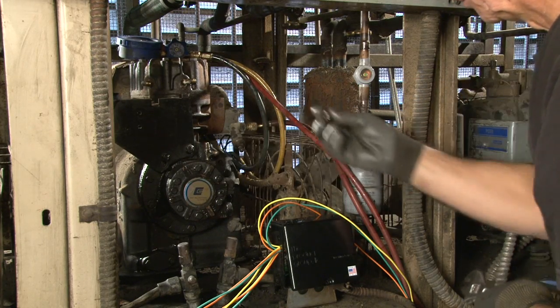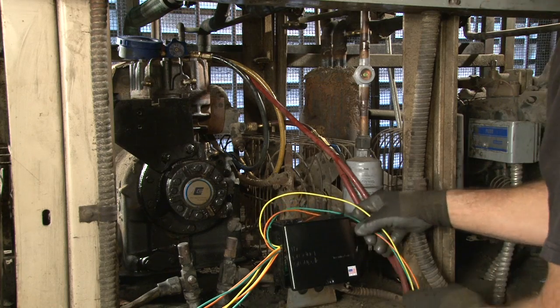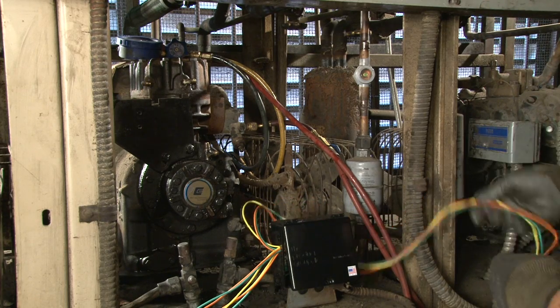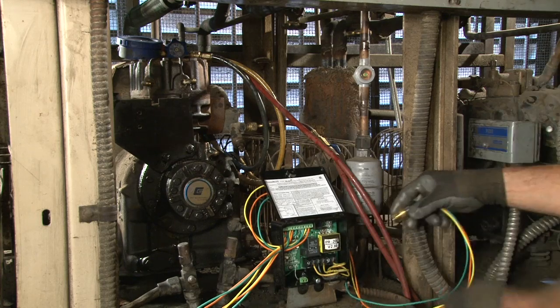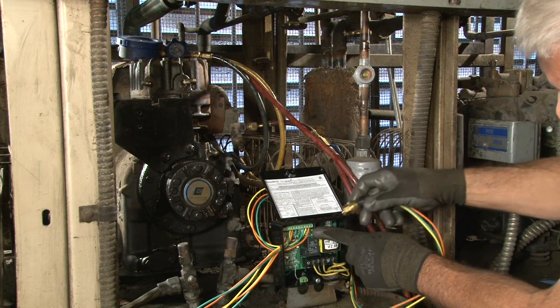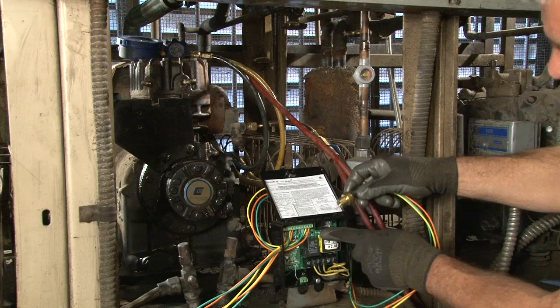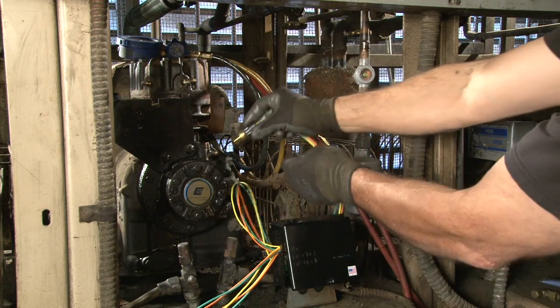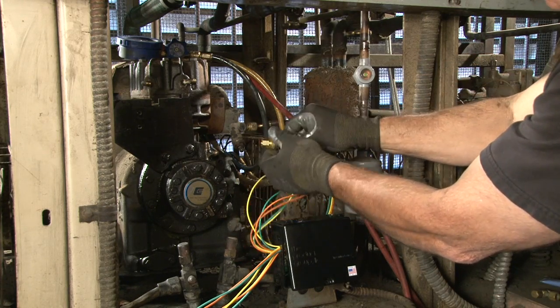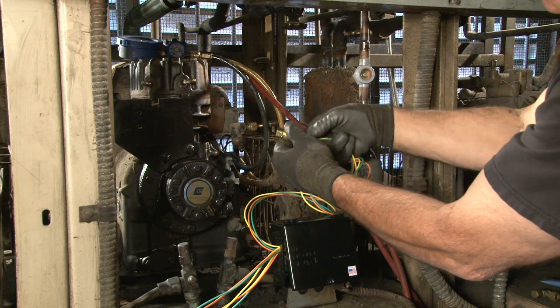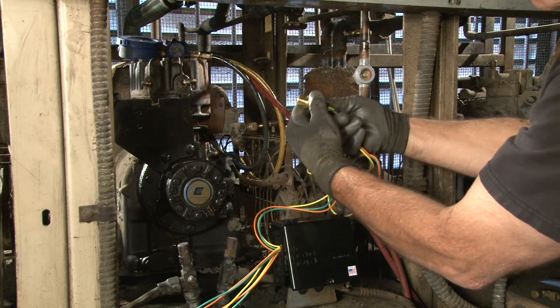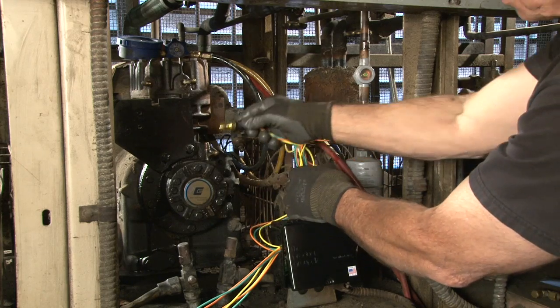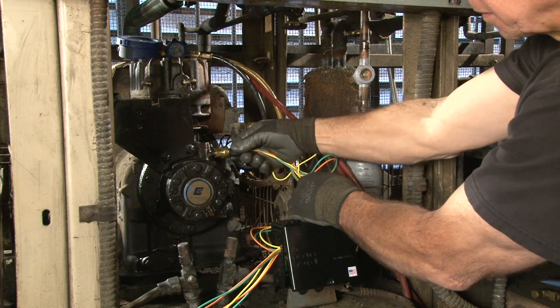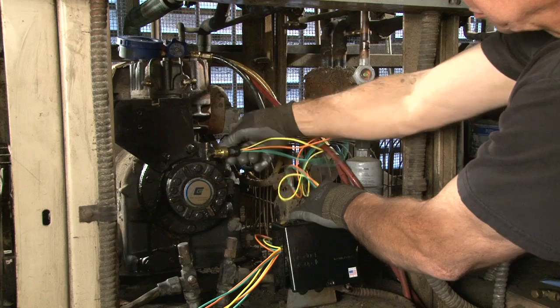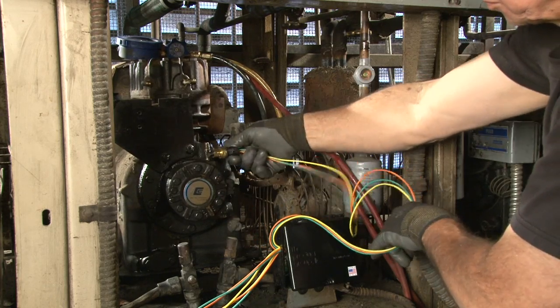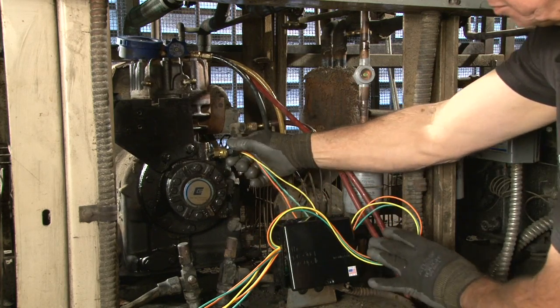He's now preparing the 1/4-inch flare ports to accept the installation of the transducers. This is critical because the transducers all need to be calibrated as they were prior to being installed on the compressor body. He's now showing that channel 4 transducer is to be installed on the discharge of the oil pump. He's backspinning the transducer wiring 7 turns approximately in order to allow easy spin-on installation onto the 1/4-inch male flare adapter fitting. Notice how the wires straighten out.